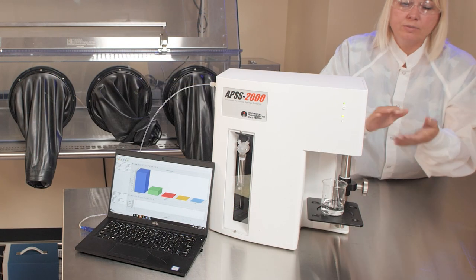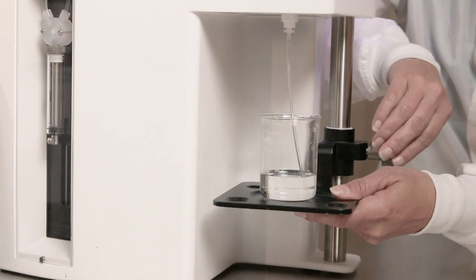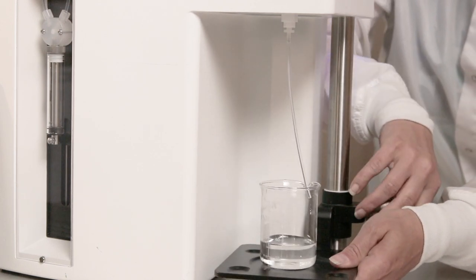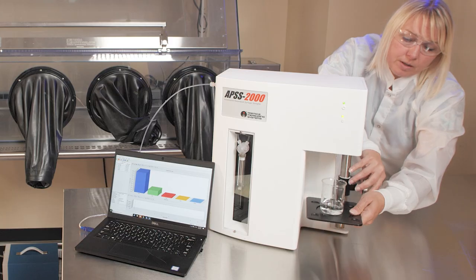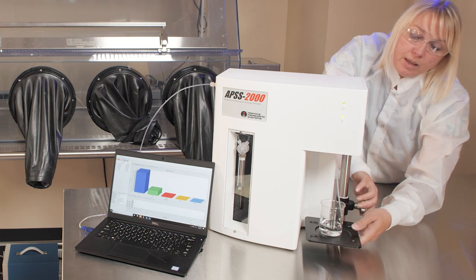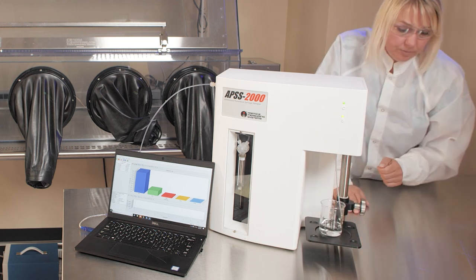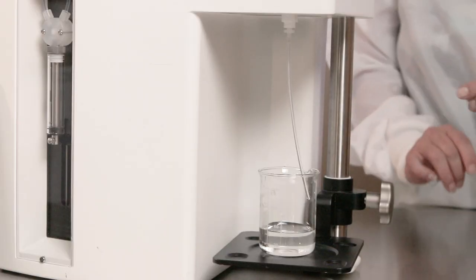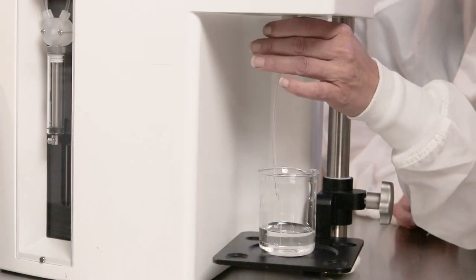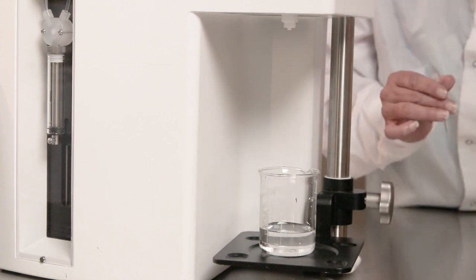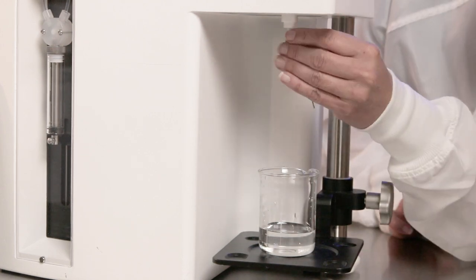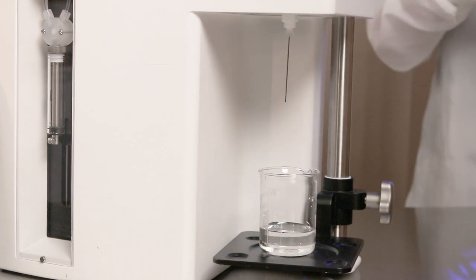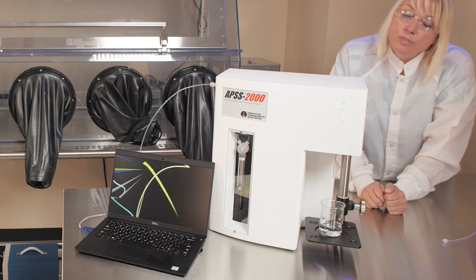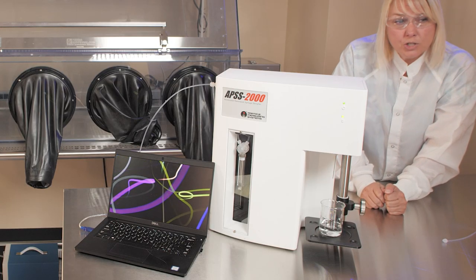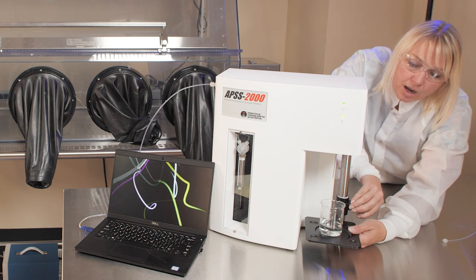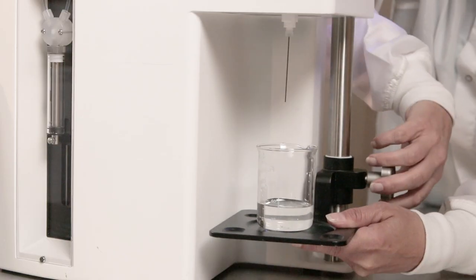The APSS-2000 has an adjustable stand. This can be raised up and down depending on the size of your sample. Has different types of syringes. This is the flexible tubing, which can be easily removed and replaced with a needle. So we have flat needles and then we have a coring needle. The coring needle can be used to puncture a sterile bag. We have different size needles.